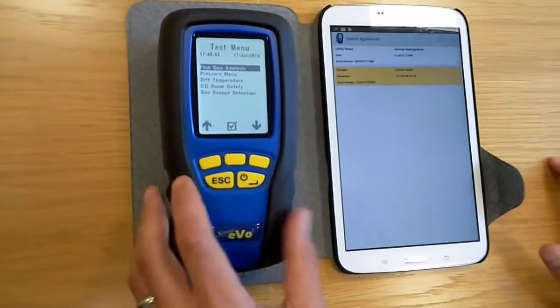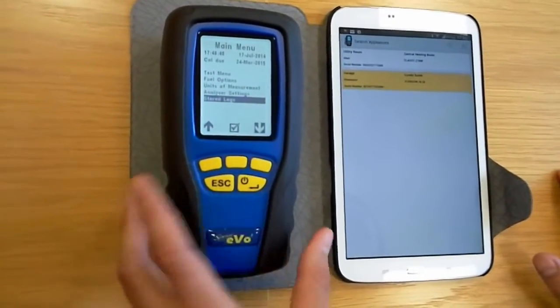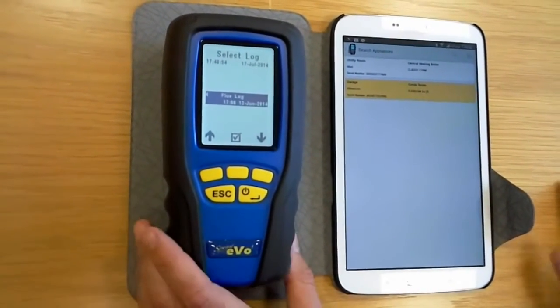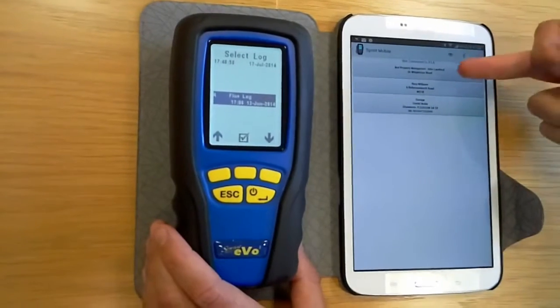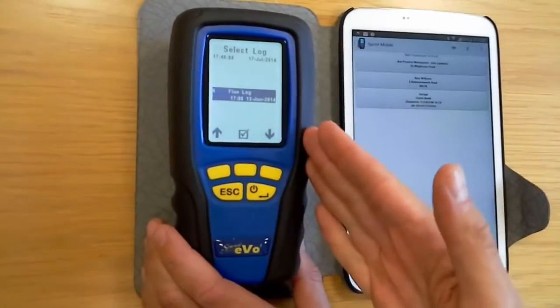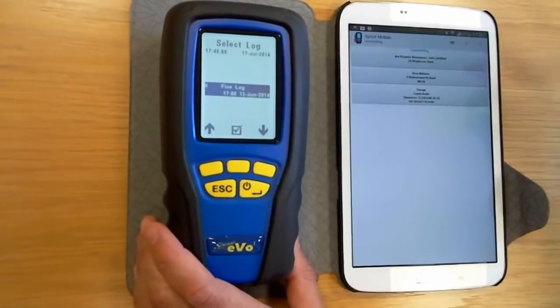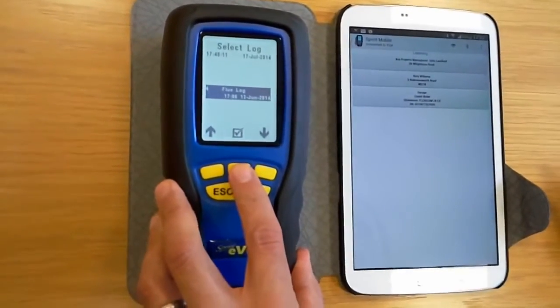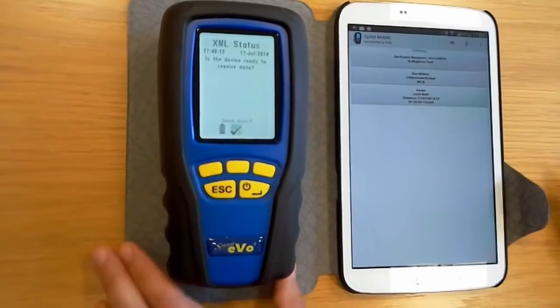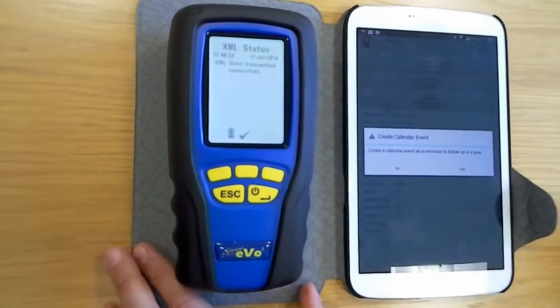Once you're up and running in flue gas mode — I'm going to pull up a stored log since this isn't live on a boiler — here's a flue gas log. Once you've selected your customer, the site, and the appliance, you're ready to take data from the analyser into Sprint Mobile. You tap that button to make sure they're listening to one another, select the log, hit the Bluetooth button, send data, and the data is instantly sent across onto the device.